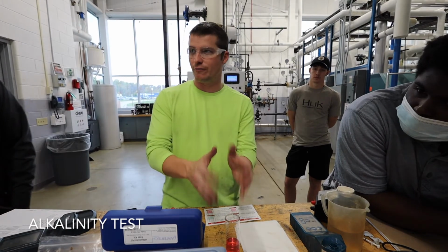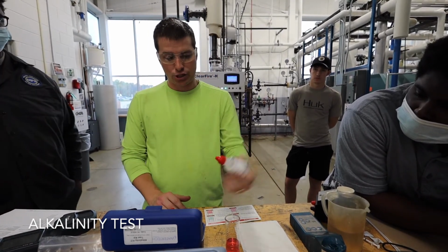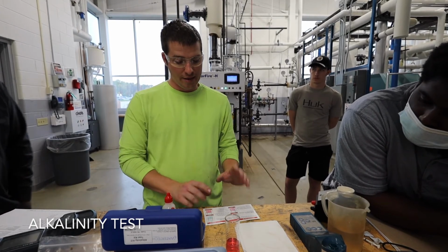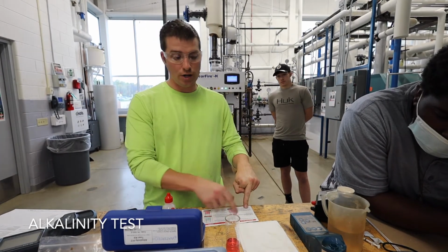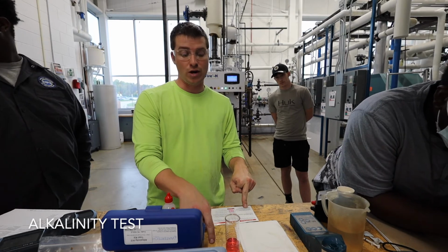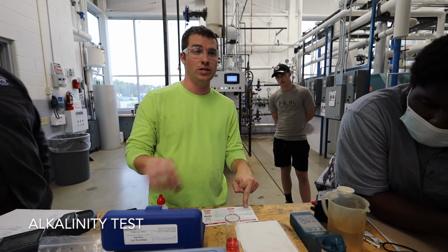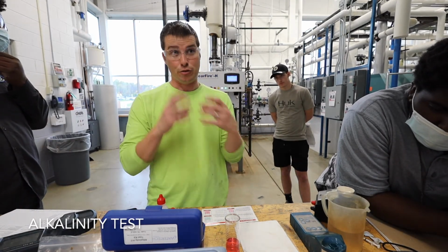If it turned green for some reason, we would then have to take our titrant again and add drops for it to go from green to pink/red. Then you need to factor in and say, okay, I was at 200, and let's say I added 2 more drops for it to go from that green to red. So 2 more drops would be 100 more parts per million of alkalinity.